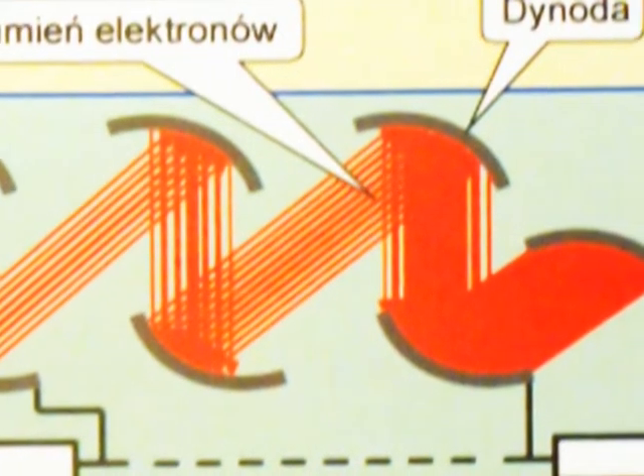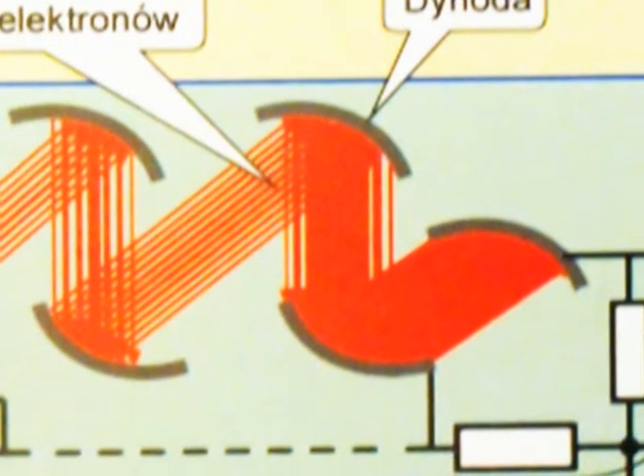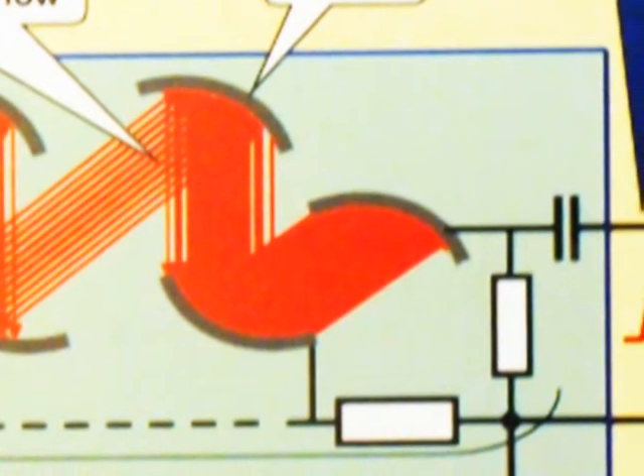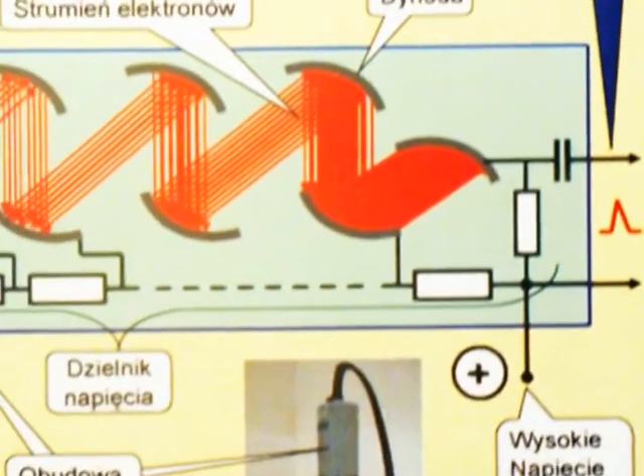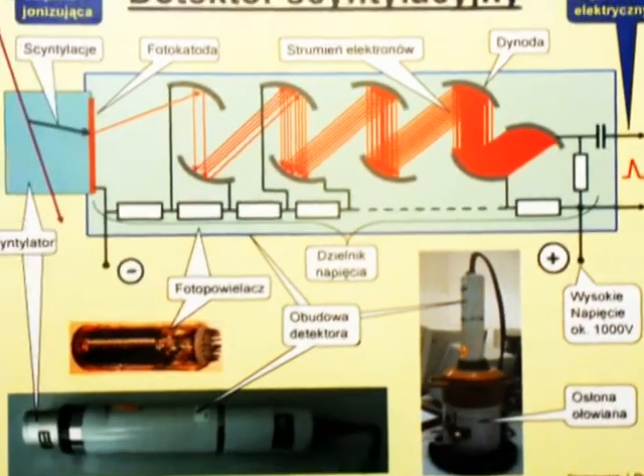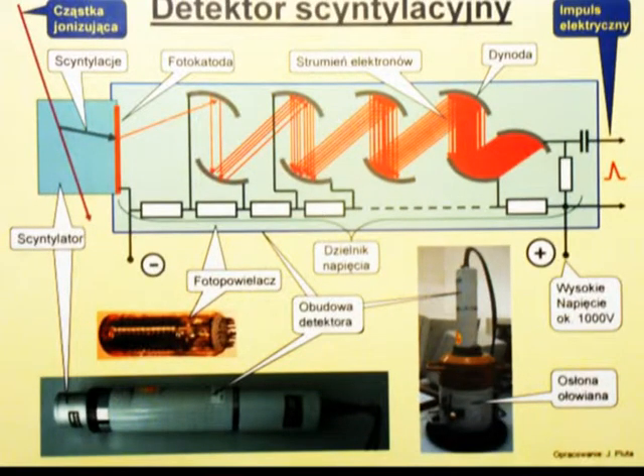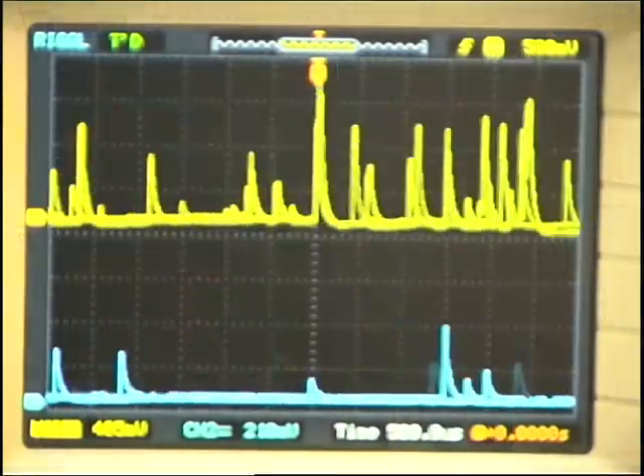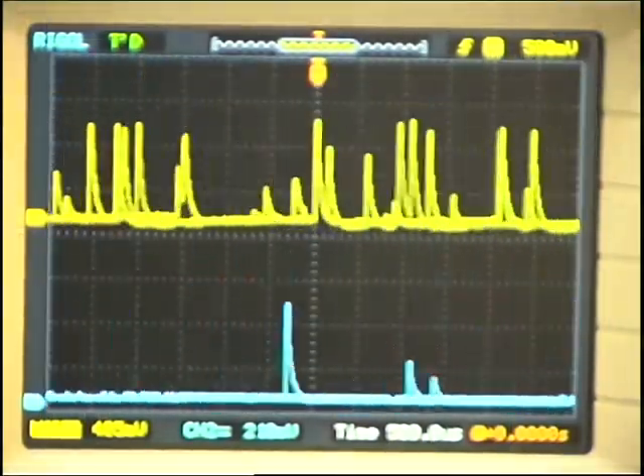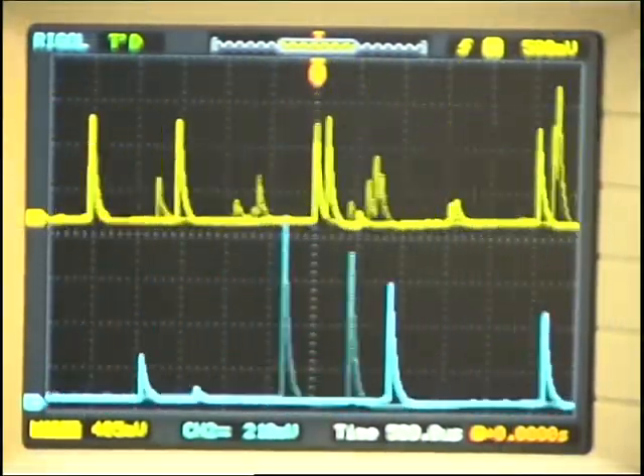This process is repeated a few times inside the photomultiplier tube. This induces on the anode a measurable macroscopic electric charge. All the instruments are attuned together to induce electric impulses with voltage values proportional to energy of a particle that comes on the crystal surface. We can observe such impulses on the oscilloscope.